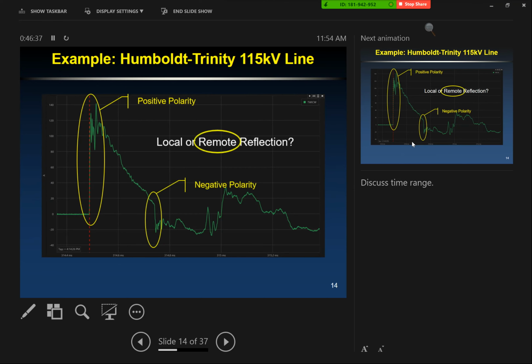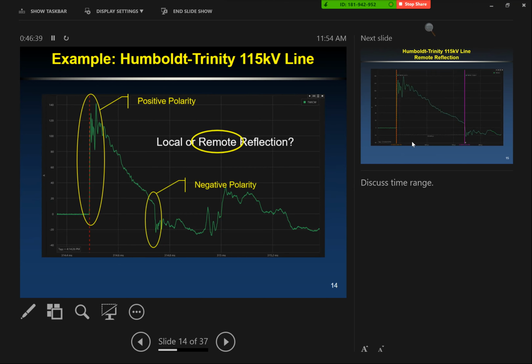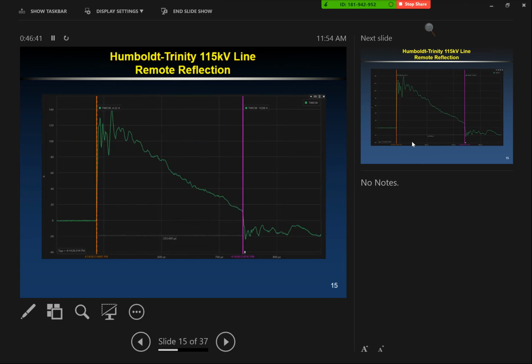So that's a remote reflection. Let's zoom in on this event and look at those two key points, the time difference between them. It's 253.4 microseconds, and we know that propagation delay corresponds to twice the distance between the fault and the remote end. So here's our distance equation.